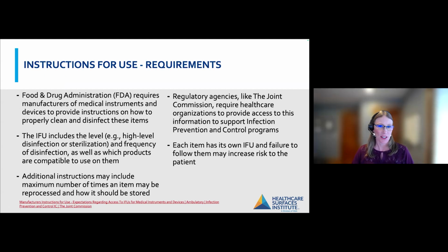So as we started to talk about just a moment ago with instructions for use, I wanted to go into a little bit more detail of what's required. As Linda alluded to, the Food and Drug Administration requires that any manufacturer of a medical device or an instrument provide instructions on how to clean and how to disinfect these items. We know that each item needs to be cleaned and disinfected in a different way based on how the piece of equipment is put together. If there are different types of surfaces, those items might need to be cleaned with a different product.